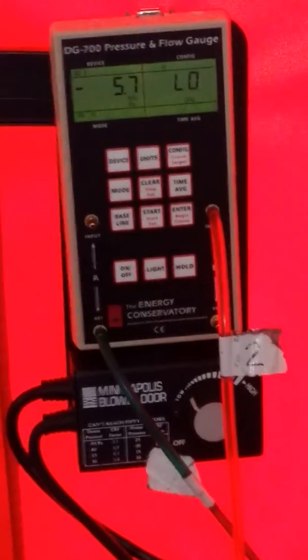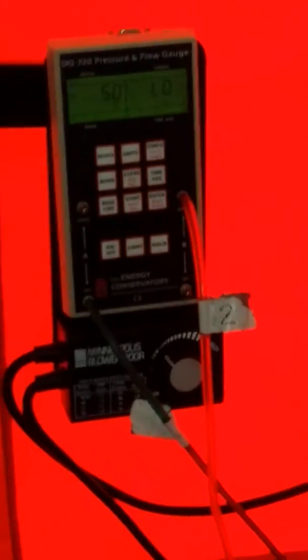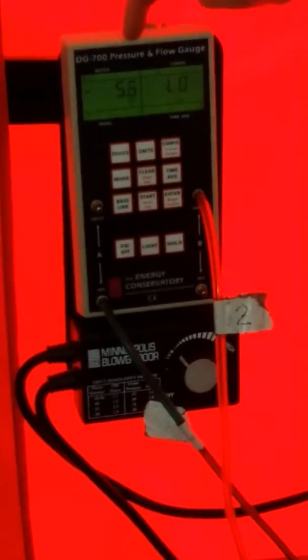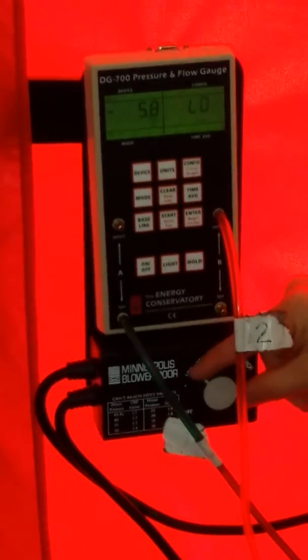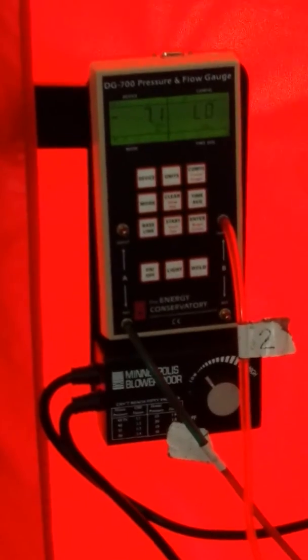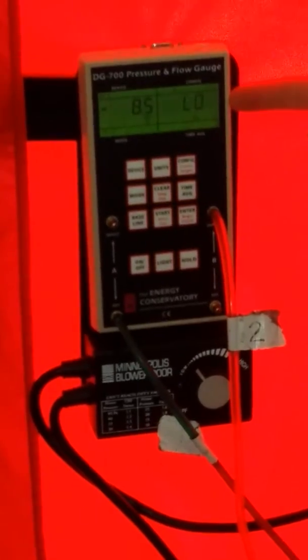Well, we're going to try not to totally constrict it. I'd like people to still be able to see, but without blocking all of the air. So if I'm standing like this, it's probably not so good. We'll give it some room so we can pull some air. That looks a little too slow. Let's pick it up. I've depressurized to about 5 pascals. Not quite enough. So what if we go a little bit more? Let's go midpoint. I'm starting to get some numbers here, but it's still flashing low over here.